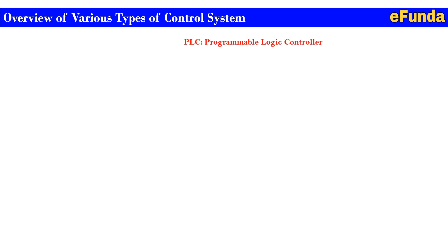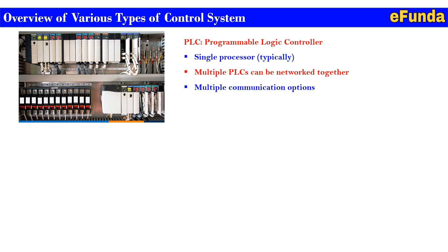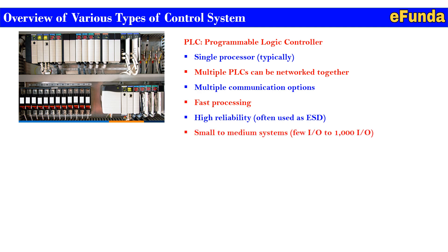The first type is the PLC, Programmable Logic Controller. One can refer to the picture to get a feel of how the PLC system looks, which consists of a single processor. Typically, multiple PLCs can be networked together. It offers multiple communication options, fast processing, and high reliability. It is often used as an emergency shutdown system and suits small to medium systems with few IOs to thousands of IOs.